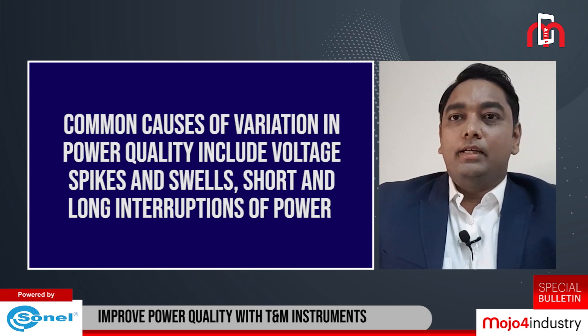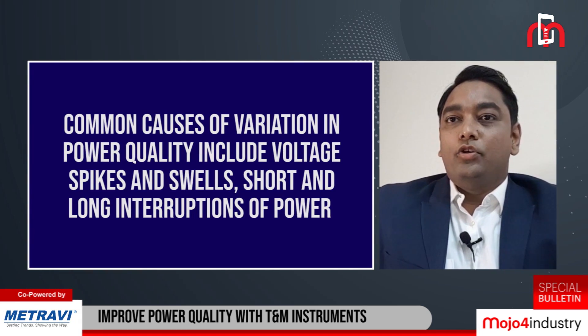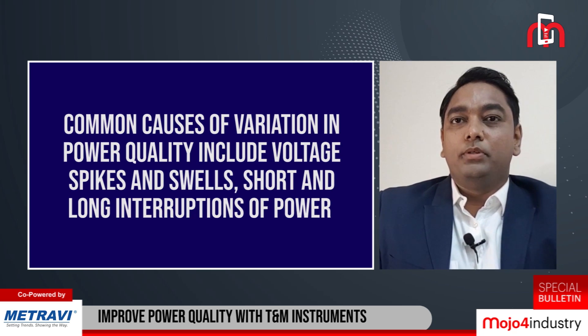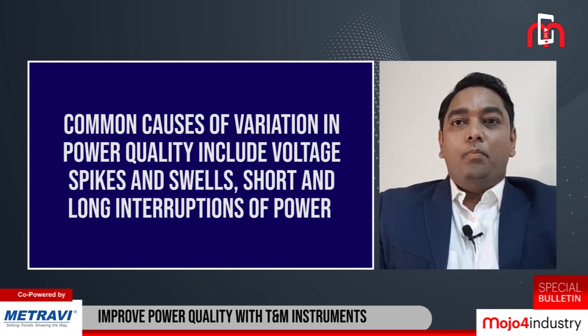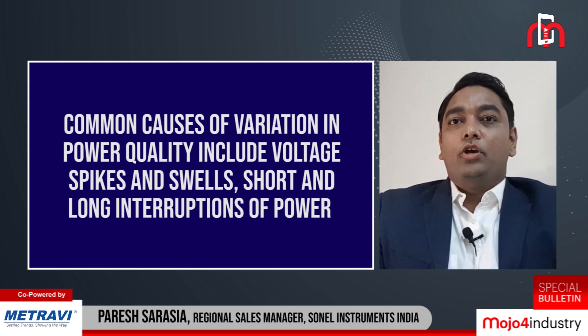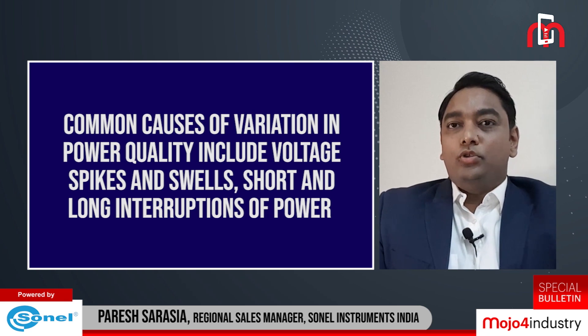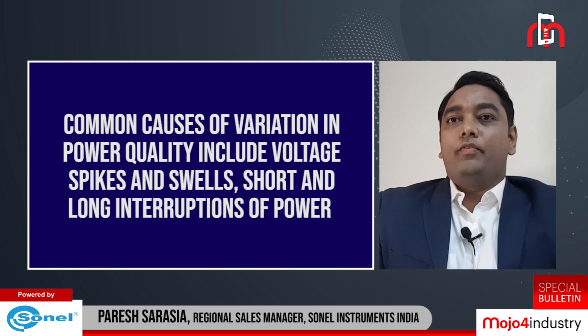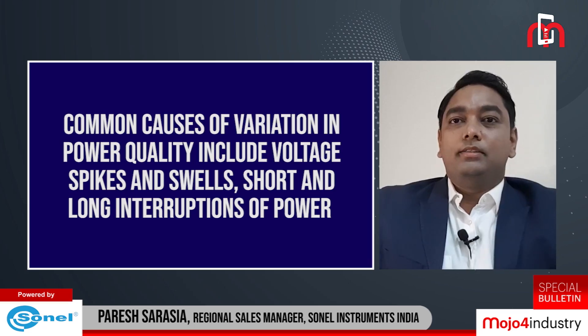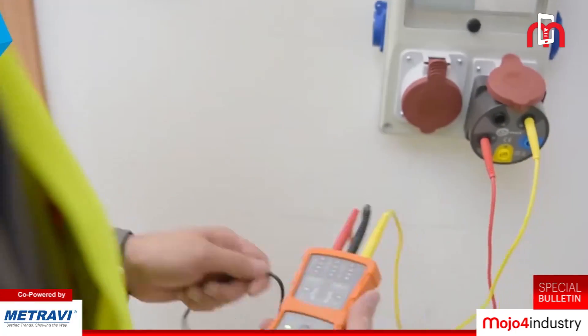Power quality analyzers provide continuous monitoring of your machines and power system to check power distribution and possible disturbances that can decrease productivity. By detecting issues early, you can fix them before they become much bigger problems. Sonel power quality analyzers can measure and record according to IEC 61000-4-30 Class A standard.